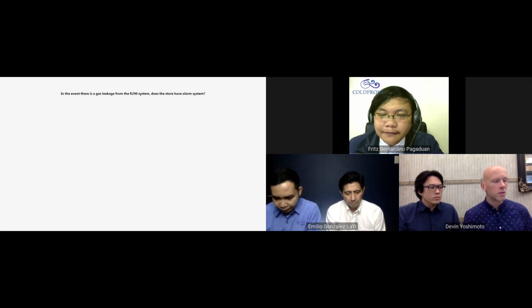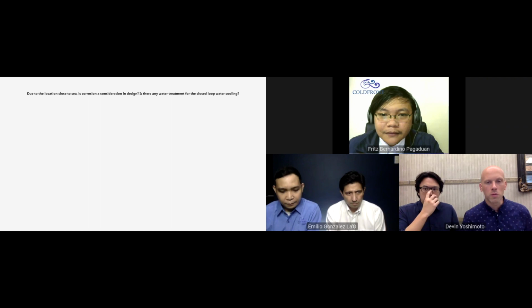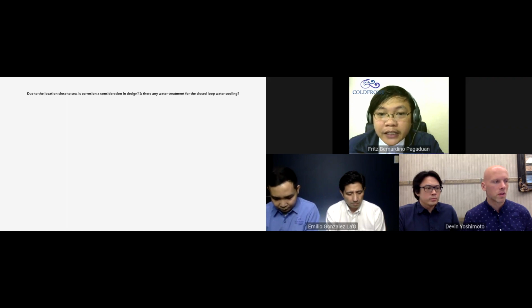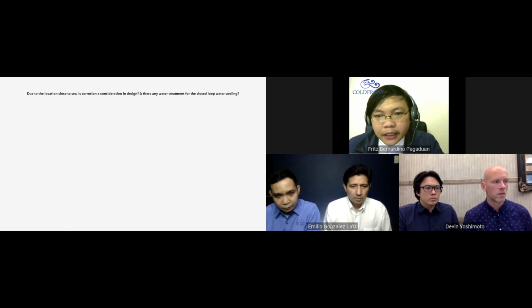Next question. Due to the location close to the sea, is corrosion a consideration in design? Is there any water treatment for the closed loop water cooling? Actually, sir, the water loop is designed as a closed loop. The principle is the same as the cooling tower, but this is a closed loop. So no foreign debris, no foreign objects, and no other chemicals except mineral water and glycol. That's why we are using mineral water and glycol. We're not using tap water because of the oxidation inside of the system.